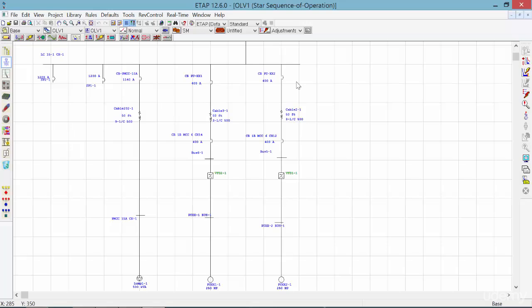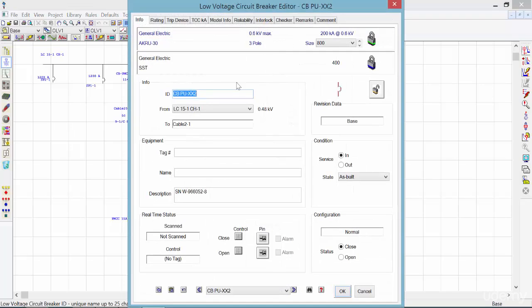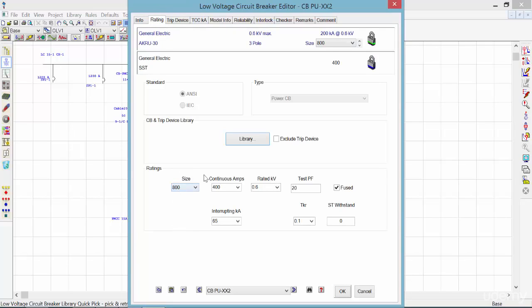So what I'm gonna do is open one of the breakers for pump number 2, CB pump XX2, and switch over to the rating to see the rating of this breaker. As you can see, the frame size of this breaker is 800 amps. The continuous amp size of the breaker and the trip of this breaker is set at 400 amps, and it's rated for 600 volts, the test power factor is 20, and the interrupting current is 65 kiloamps, and so on and so forth.